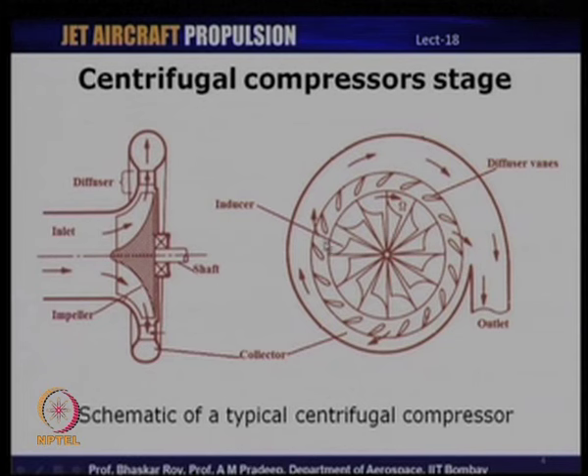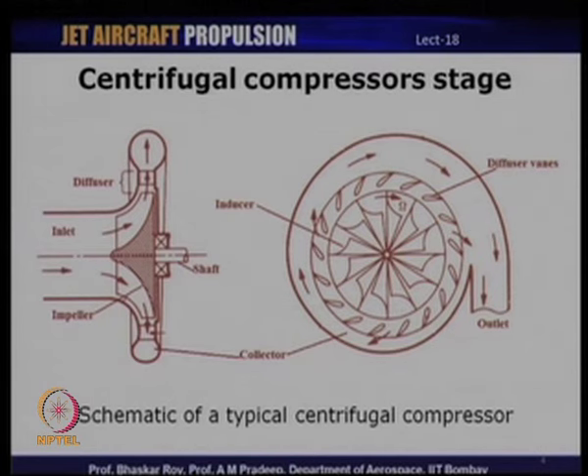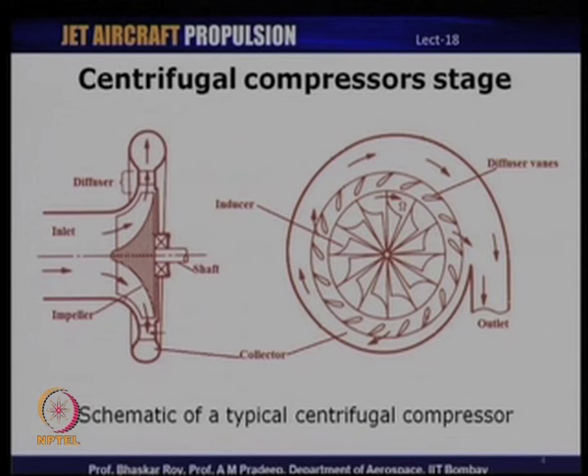Another component shown here is known as the inducer. The inducer is one part of an impeller — it is meant to guide the flow smoothly into the impeller. In the absence of an inducer, the flow might enter the impeller with an abrupt change of direction, leading to noise and efficiency loss. I will now show two typical centrifugal compressor rotor photographs representing two different types.